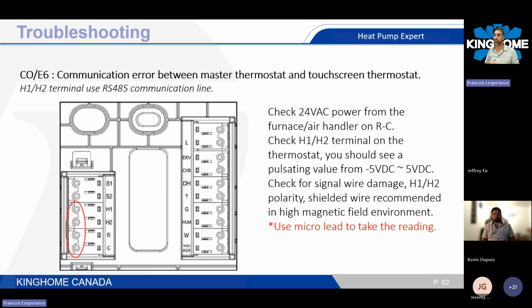So you don't have to have a shielded wire, but it will be recommended if you are in a high magnetic field environment. So sometimes it's really just because you are near a plant, or there's some high magnetic field around you. So maybe sometimes that can create a communication issue. So at that moment, using a shielded wire will help you out. But for main purpose, you won't need to have a shielded wire.